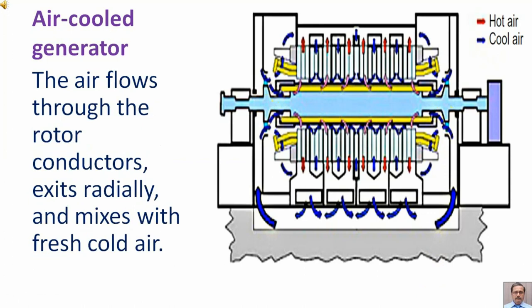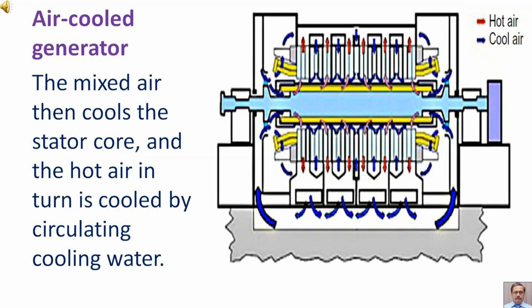The air flows through the rotor conductors, exits radially and mixes with fresh cold air. The mixed air then cools the stator core and the hot air in turn is cooled by circulating cooling water.